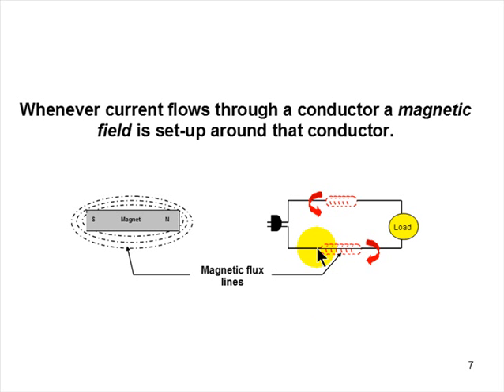Because the clamp-on amp probe doesn't count the number of electrons that pass that point. What it does is read the intensity of the magnetic field. Because the more electrons that go past that point where you've connected that clamp-on amp probe, the more that pass through there, the greater that magnetic field is going to be, and that needle is going to swing left or right depending on the intensity. And that's all a clamp-on ammeter does, is read the intensity of that magnetic field.